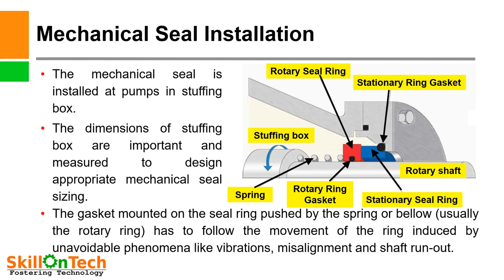A picture of mechanical seal installation is shown in the slide. The mechanical seal is installed at pumps in the stuffing box. The dimensions of the stuffing box are important and are measured to design appropriate mechanical seal sizing. The size of the mechanical seal depends on the dimensions of the stuffing box. The gasket mounted on the seal ring is pushed by the spring or bellows, and the gasket is mounted on the shaft sleeve at the rotary seal ring. The assembly has to follow the movement of the ring, induced by unavoidable phenomena like vibrations, misalignment, and shaft runout.